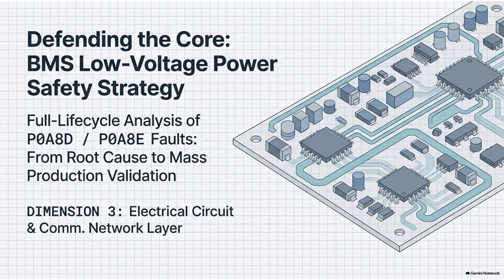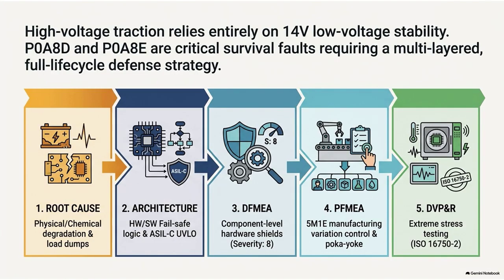Sure. With lead-acid chemistry especially, you're constantly fighting plate sulfation. As these lead sulfate crystals grow and harden on the plates, they reduce the active surface area. And simultaneously, you've got vibration and thermal cycling causing the physical shedding of that active material. Right. And from a circuit analysis perspective, that physical degradation translates directly to a massive spike in internal electrical impedance. Yes, exactly. Because a healthy battery essentially acts as a giant decoupling capacitor for the entire low-voltage grid.